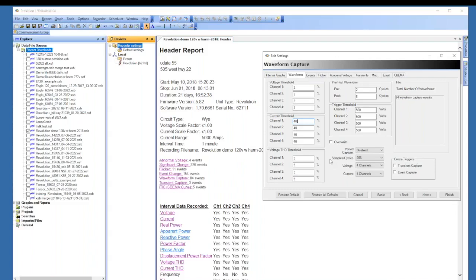Anything approaching 5%, you may want to start then looking at individual harmonics. But if it goes over 5%, you definitely want to record individual harmonics and see which harmonics are causing that. But overall, you want a VTHD of less than 5%.